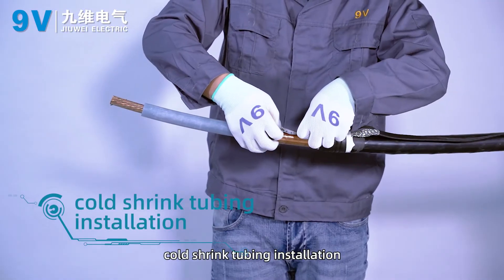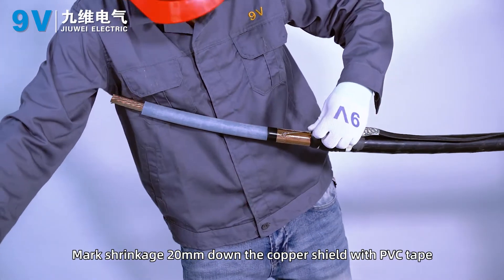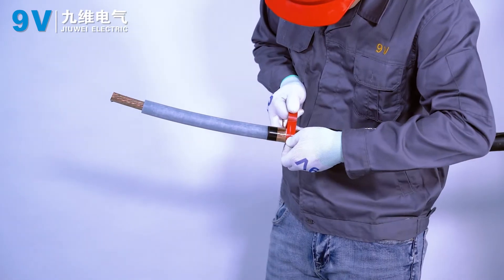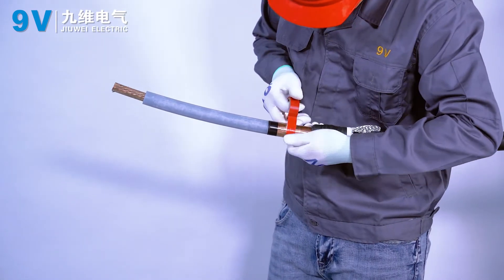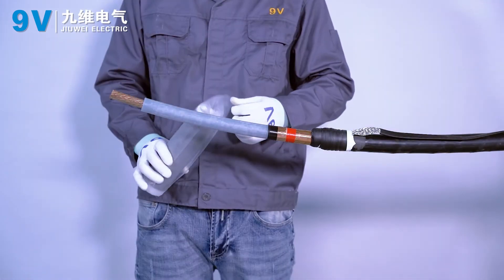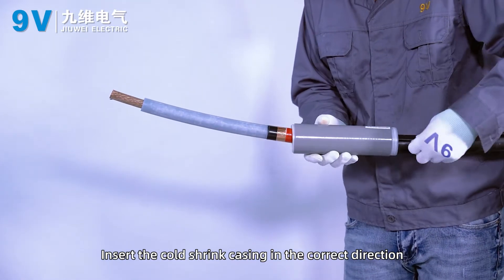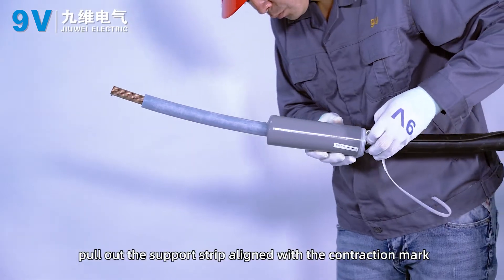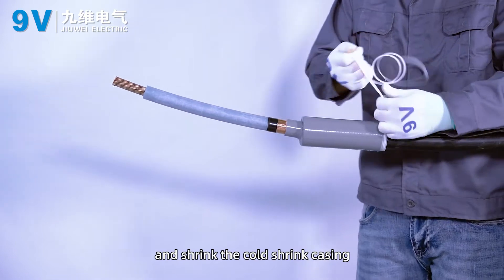Cold shrink tubing installation. Mark 20 mm down the copper shield with PVC tape to indicate the shrinkage position. Insert the cold shrink casing in the correct direction. Pull out the support strip aligned with the contraction mark and shrink the cold shrink casing.